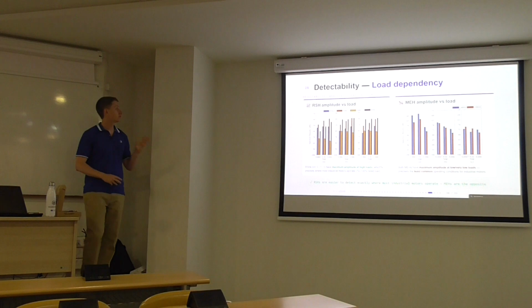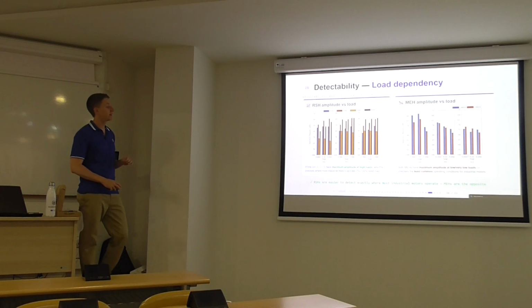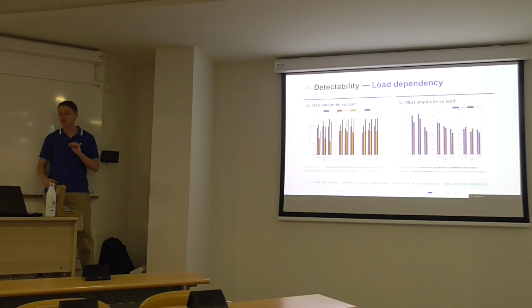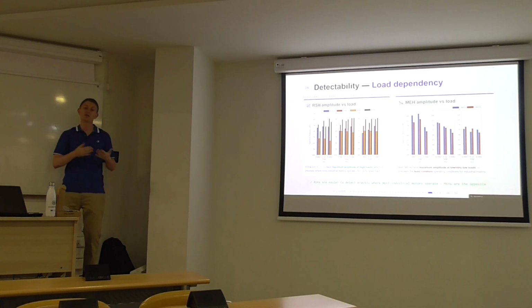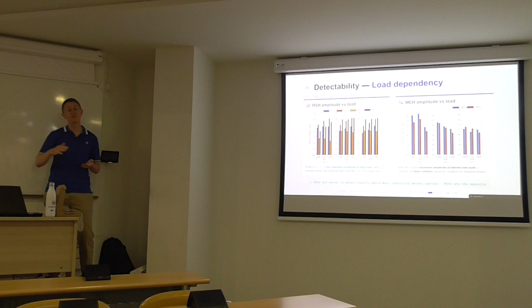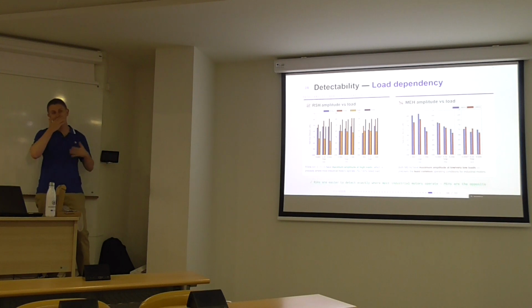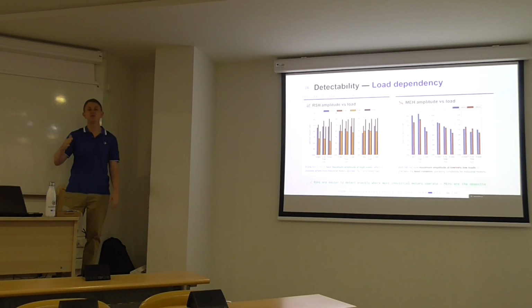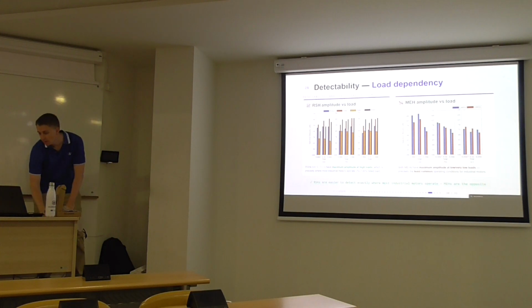So, in summary, rotor slot harmonics are easier to detect exactly where most industrial motors operate, which is what we want. If the mixed eccentricity harmonic is most detectable at low loads, there is a problem, because few motors operate at low loads. The majority of them operate maybe between 60 and 100% of the rated current.